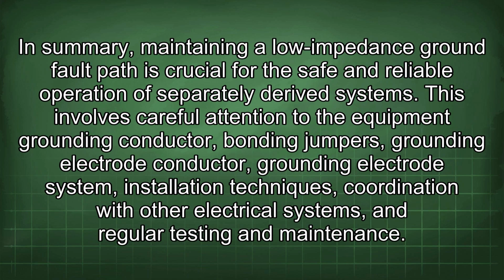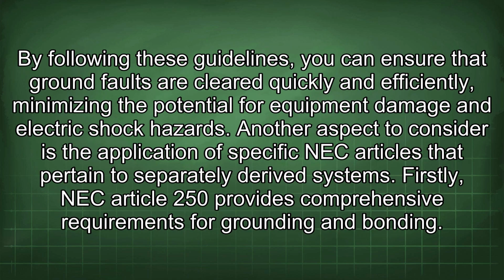In summary, maintaining a low-impedance ground fault path is crucial for the safe and reliable operation of separately derived systems. This involves careful attention to the equipment grounding conductor, bonding jumpers, grounding electrode conductor, grounding electrode system, installation techniques, coordination with other electrical systems, and regular testing and maintenance. By following these guidelines, you can ensure that ground faults are cleared quickly and efficiently, minimizing the potential for equipment damage and electric shock hazards.